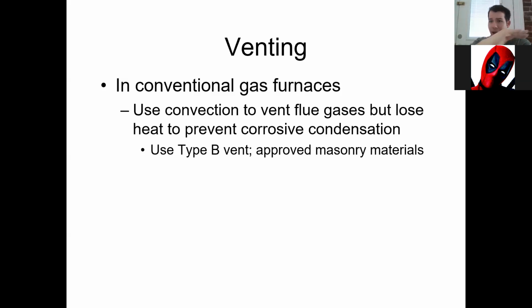And I know all those little turns are spots where it's going to lose speed. The airflow is going to slow down, and because that airflow is slowing down, it's going to cool off and condense. In each 90, you have a higher chance of condensate gathering and eating through that metal than any other section of that flue piping, just because that's how it's designed.